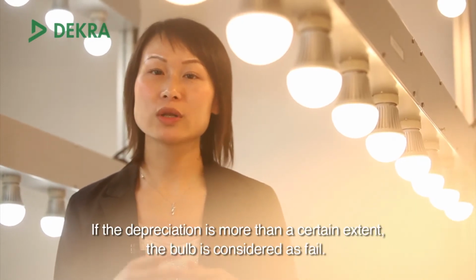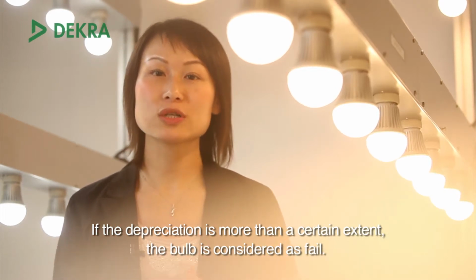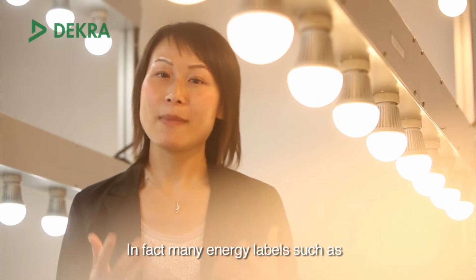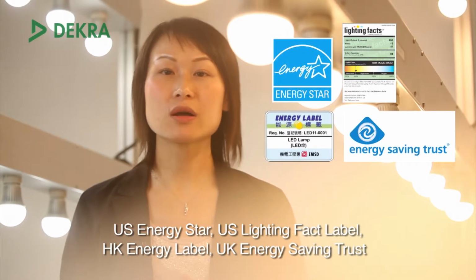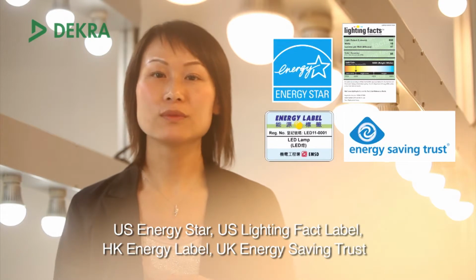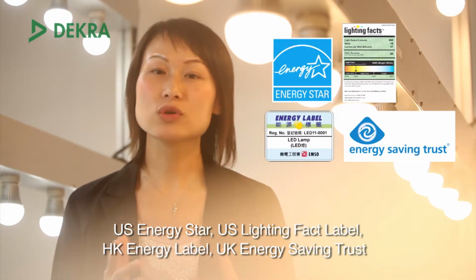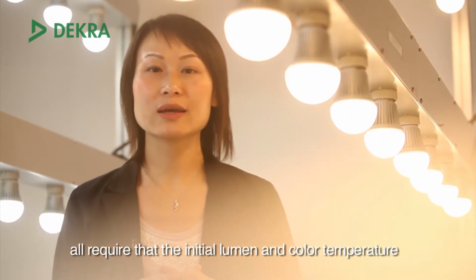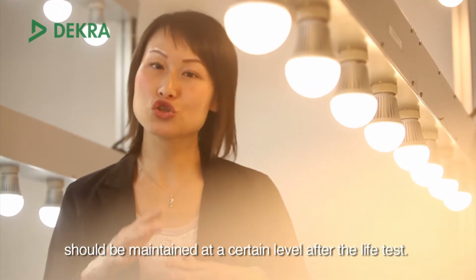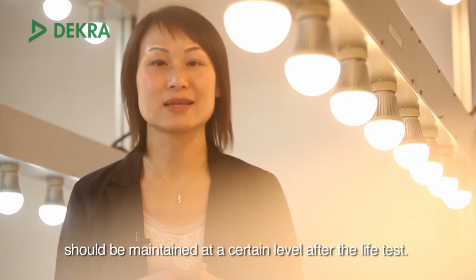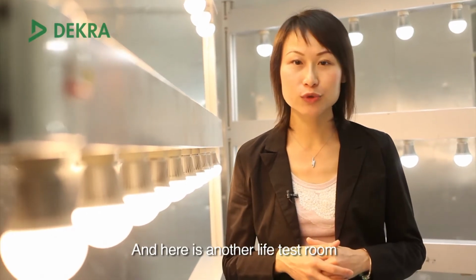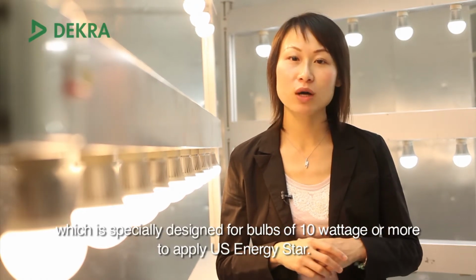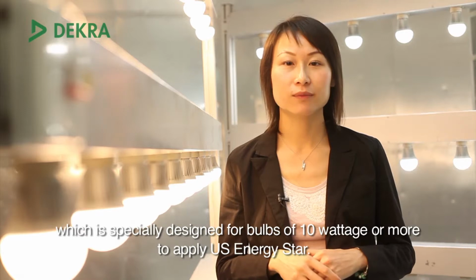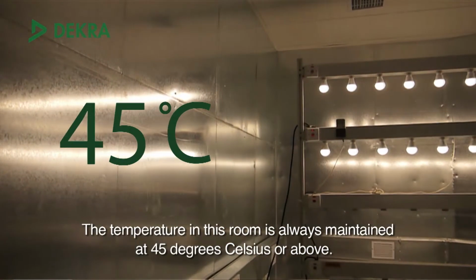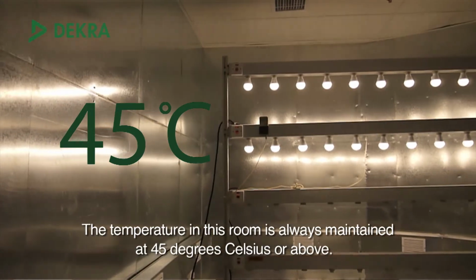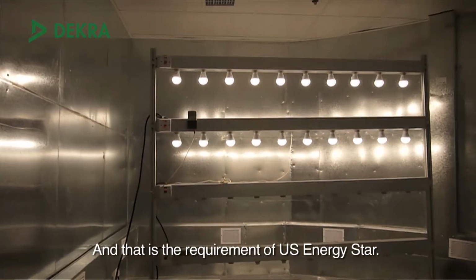If the depreciation is more than a certain extent, the bulb is considered as fail. In fact, many energy labels such as US Energy Stars, US Lighting Facts label, Hong Kong Energy label, and UK Energy Saving Trust all require that the initial lumen and color temperature should be maintained at a certain level after the life test. And here is another life test room which is specially designed for bulbs of 10 wattage or more to apply US Energy Star. The temperature here in this room is always maintained at 45 degrees Celsius or above, and that is the requirement of US Energy Star.